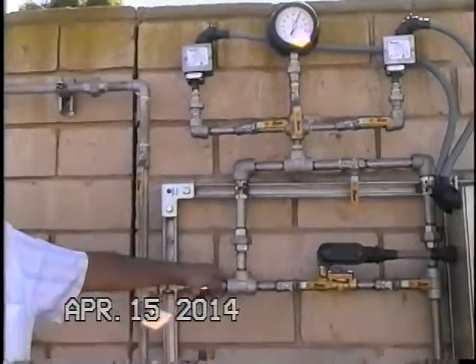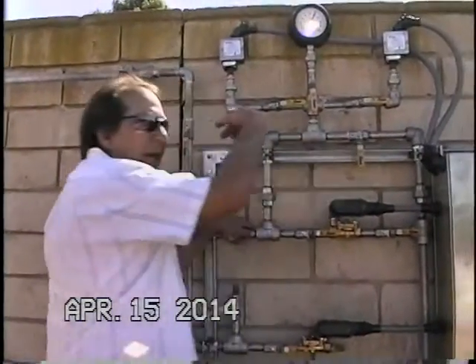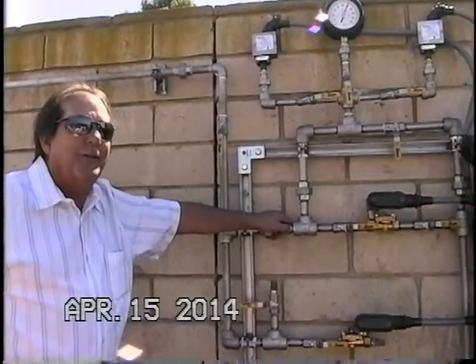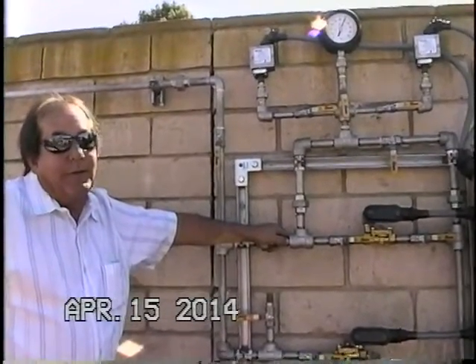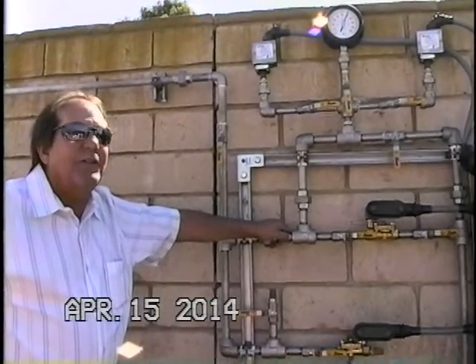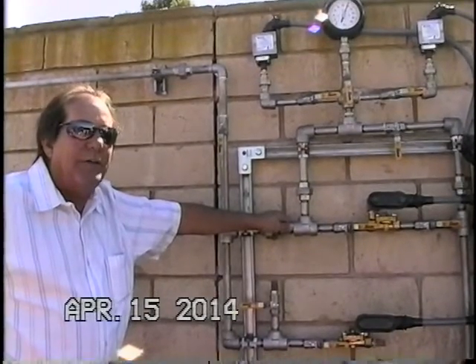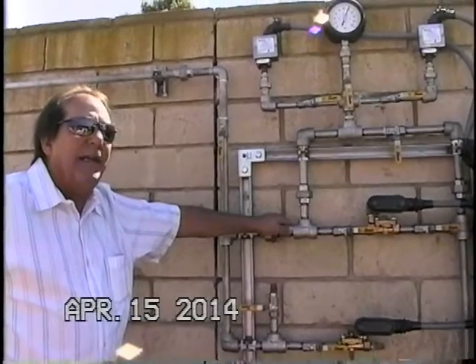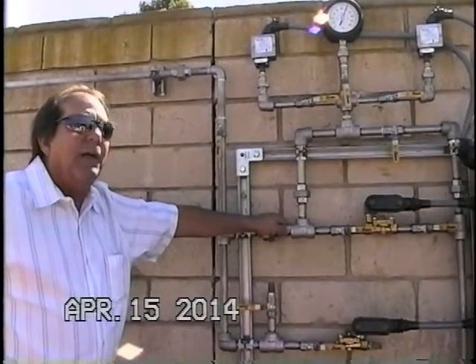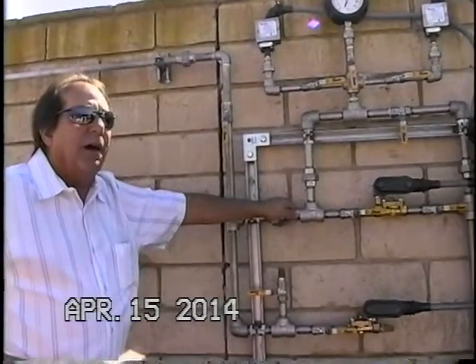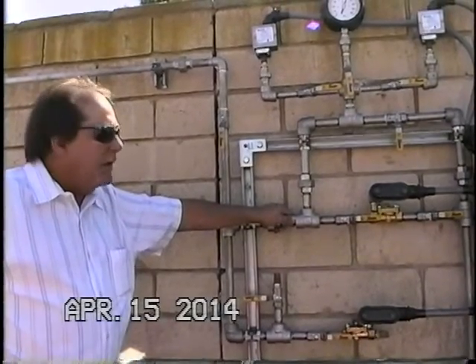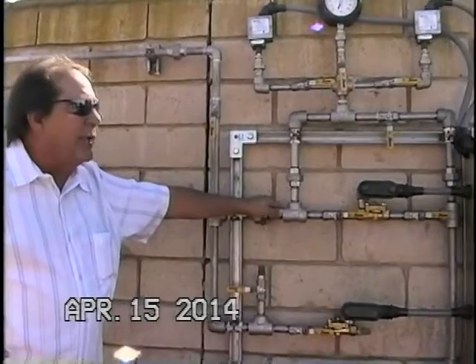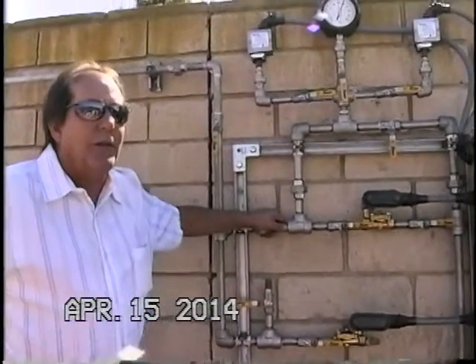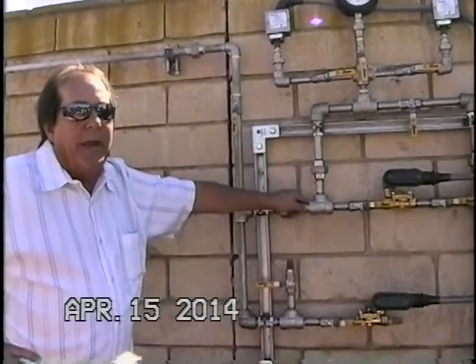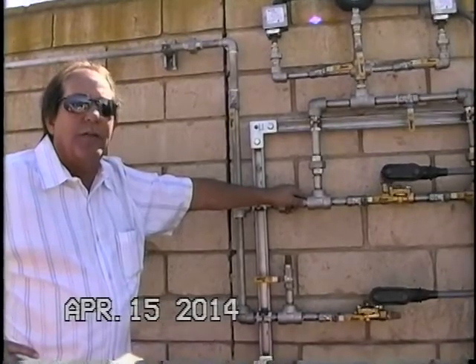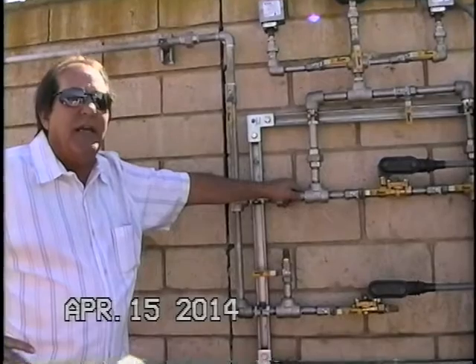It could be as simple as somebody had the discharge valve off, left a bypass, or added air. We created a high pressure condition because maybe your operator just forgot. Typically we shouldn't see any high pressure conditions, because these pressure switches are set higher than any anticipated surge condition. It would definitely be an abnormal condition if you got a high pressure alarm. A low pressure alarm, on the other hand, could have a simple reason: you've taken the system out of service and drained the air pressure for maintenance or something of that nature. Otherwise, you shouldn't see either of those two conditions at all.